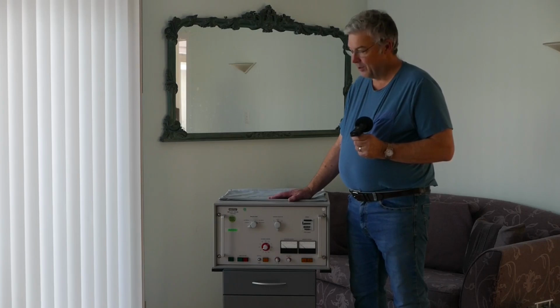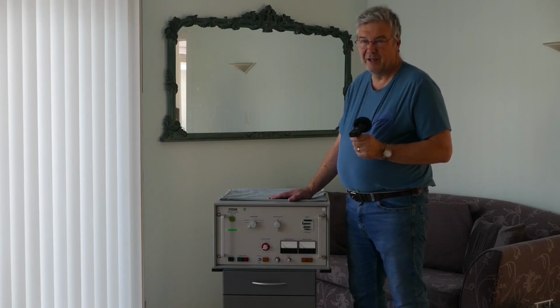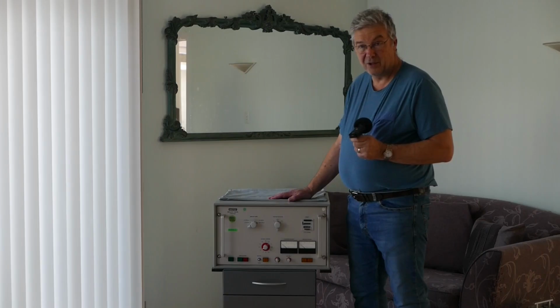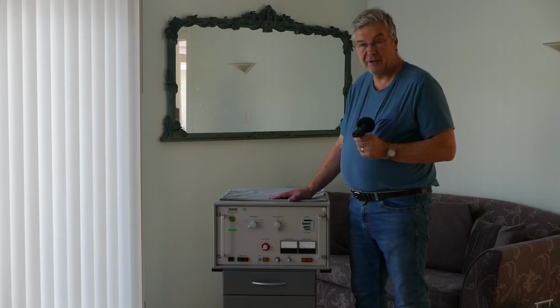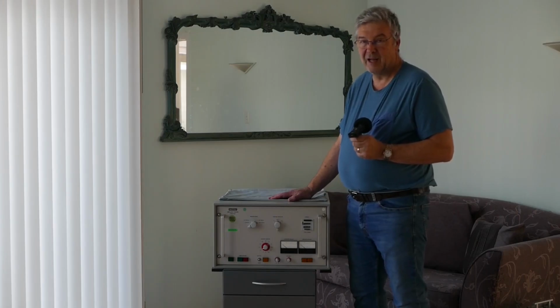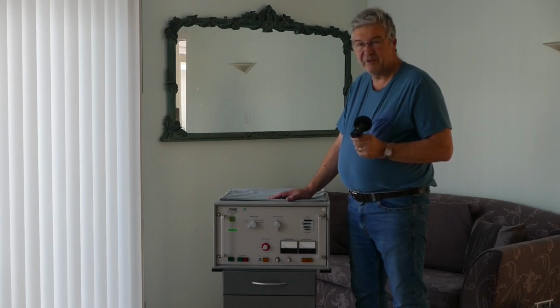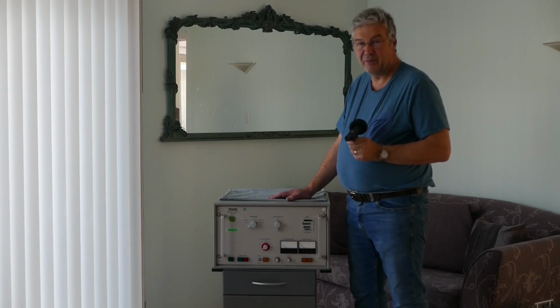supply. So this would be used to test equipment such as telephone equipment that is hooked up to the telephone network. These days it would be used to test solar powered systems to make sure that those systems are able to withstand normal transients coming down the mains, and any other equipment that you would expect to connect to the main system. I'm opening this unit up today to do a safety inspection. My aim is to make sure that it is safe to connect to the mains, and that was also an opportunity to take a look and see what's inside. So let's get to it.